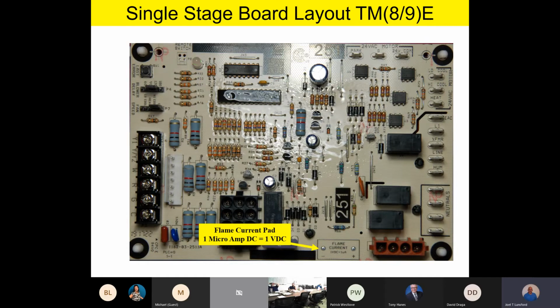And 1 volt DC equals 1 microamp of flame current. So now the meter they have on their truck, a volt-ohm meter more than likely, will do. Any technician doing this is going to have a voltmeter. So instead of having a special meter, you can just go in with your voltmeter on a DC voltage scale and read the flame current right off the board, which I think is a really slick feature on our Champion furnace.